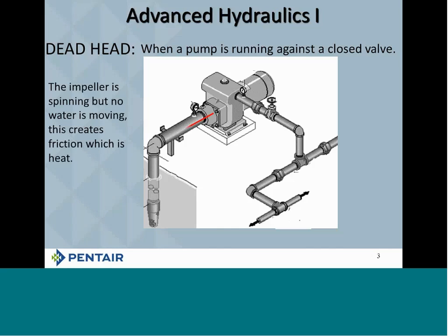So you have to remember that on the suction side of the pump, because water is a very good conductor of heat, that heat's going to go down the suction pipe. And of course, you have to remember that it's going to go down the discharge pipe too, to wherever the plug happens to be. One guy mentioned to me one time that he had an impeller that melted down, deadheading the pump, and he melted the impeller down.